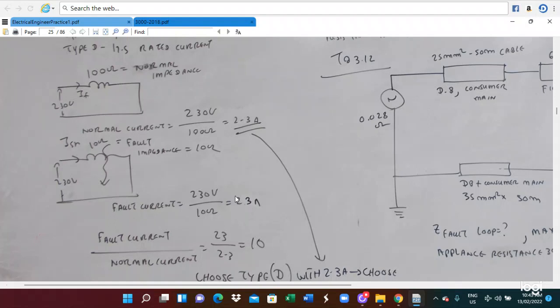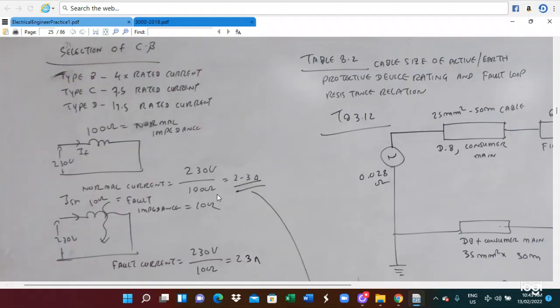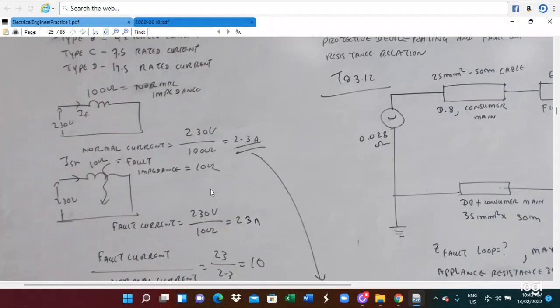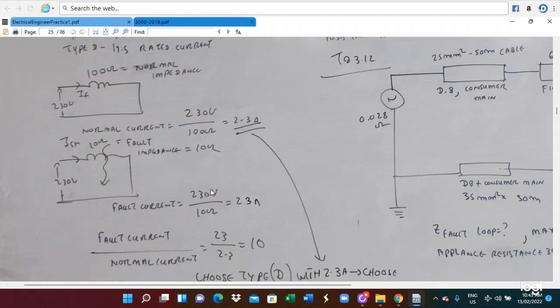Then you can see the kinds of circuit breaker: type B, type C or type D. We have to use type D because the ratio between the fault current and the normal current is 10, so type D is suitable. So you have to select type D. And what about the current? The normal current is 2.3 ampere. This 2.3 ampere and type D.